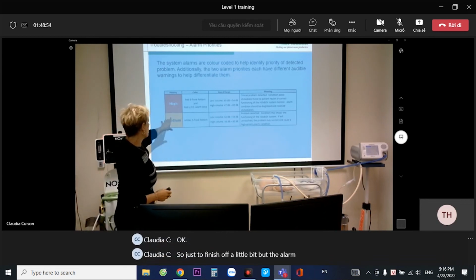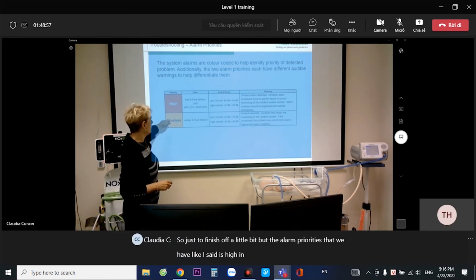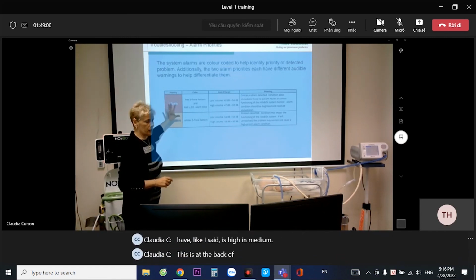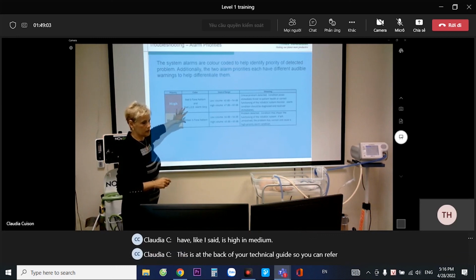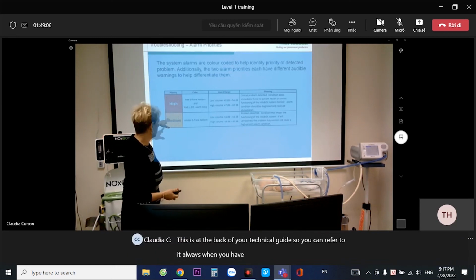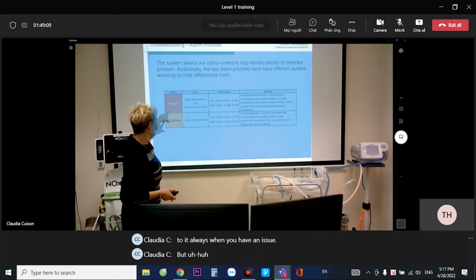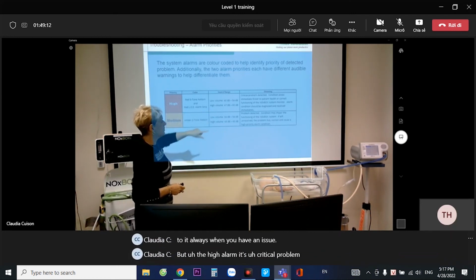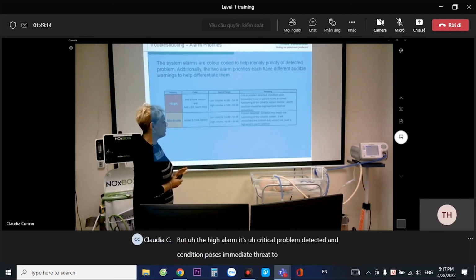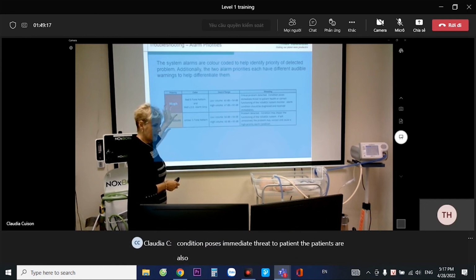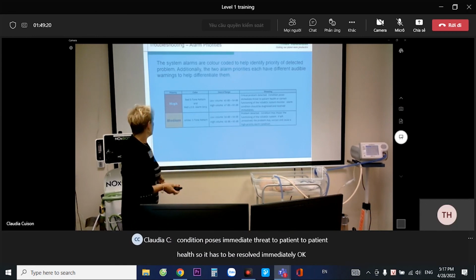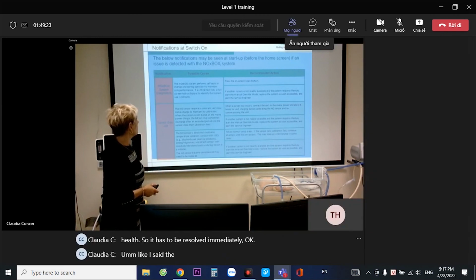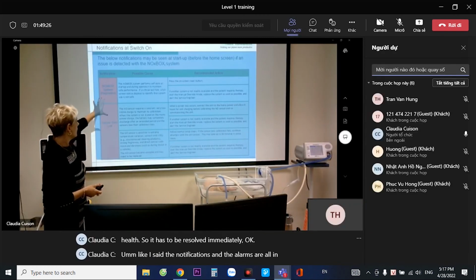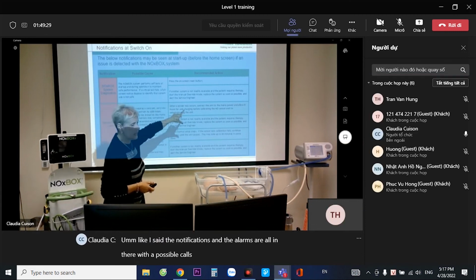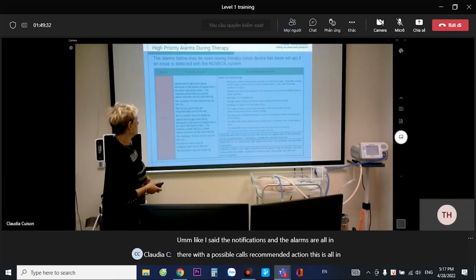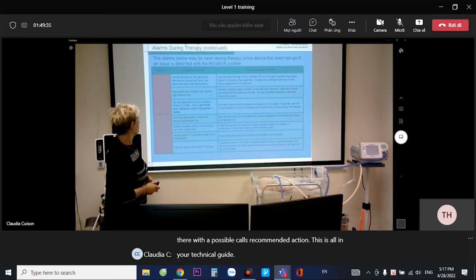So just to finish off a little bit, the alarm priorities that we have, like I said, are high and medium. This is at the back of your technical guide, so you can always refer to it when you have an issue. But the high alarm, it's a critical problem detected and the condition poses an immediate threat to the patient's health. So it has to be resolved immediately. Okay. Like I said, the notifications and the alarms are all in there with the possible causes and recommended action. This is all in your technical guide.